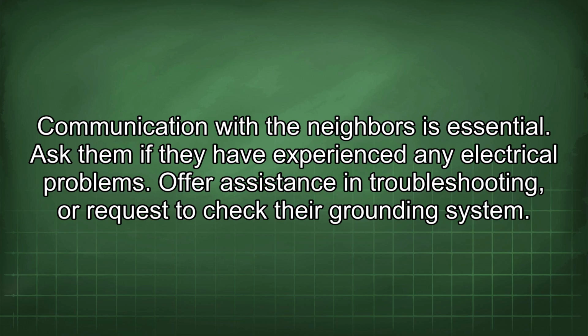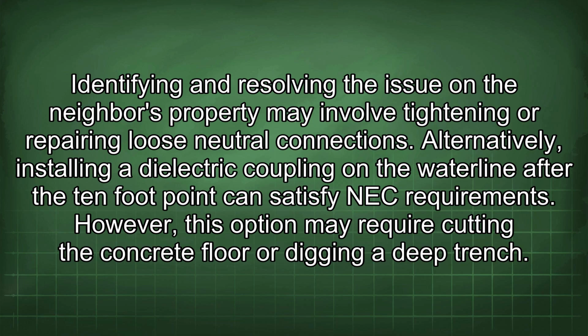Communication with the neighbors is essential. Ask them if they have experienced any electrical problems. Offer assistance in troubleshooting, or request to check their grounding system. Identifying and resolving the issue on the neighbor's property may involve tightening or repairing loose neutral connections. Alternatively, installing a dielectric coupling on the waterline after the 10-foot point can satisfy NEC requirements.